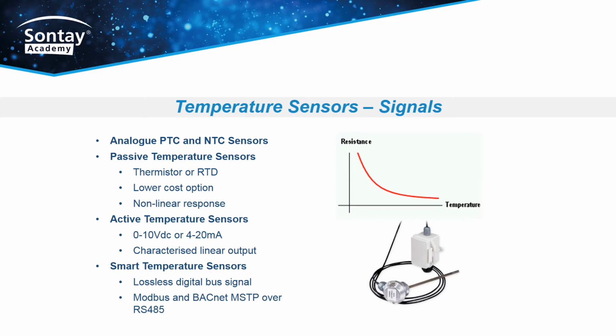For HVAC, the most common type of passive sensor is a thermistor, a thermal resistor, which provides a varying resistance as its temperature changes. Resistive temperature detectors, or RTDs, are similar to thermistors in that their resistance changes with temperature, but there are some differences. RTDs show a very small shift in resistance over their sensing range. The response is relatively linear and they have a positive temperature coefficient, which means that as the temperature increases, the resistance of the detector increases.